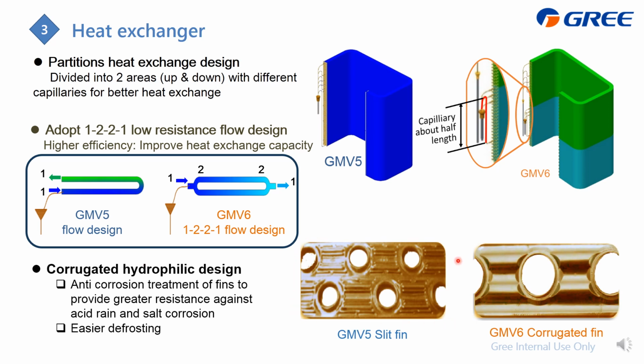And next is for the fin features. And for GMV5 is slit fin. You can find on the surface, we just make lots of the slits on the surface. And for GMV6, we just make the fin to be uneven. And from the heat transfer efficiency, definitely GMV5 is higher. However, in heating mode, as the outdoor heat exchanger, there will generate the condensing water. In low temperature situation, it will become ice, which means the ice will stick on the surface of the fin. And if there are lots of the slits here, when we do the defrost, which will make the ice to become water, and the water will not flow out easily because they will just stick on this slit. And then next time when it is going back to heating, this will cool down again and become ice easily, which means for heating performance, slip fin is not that good.